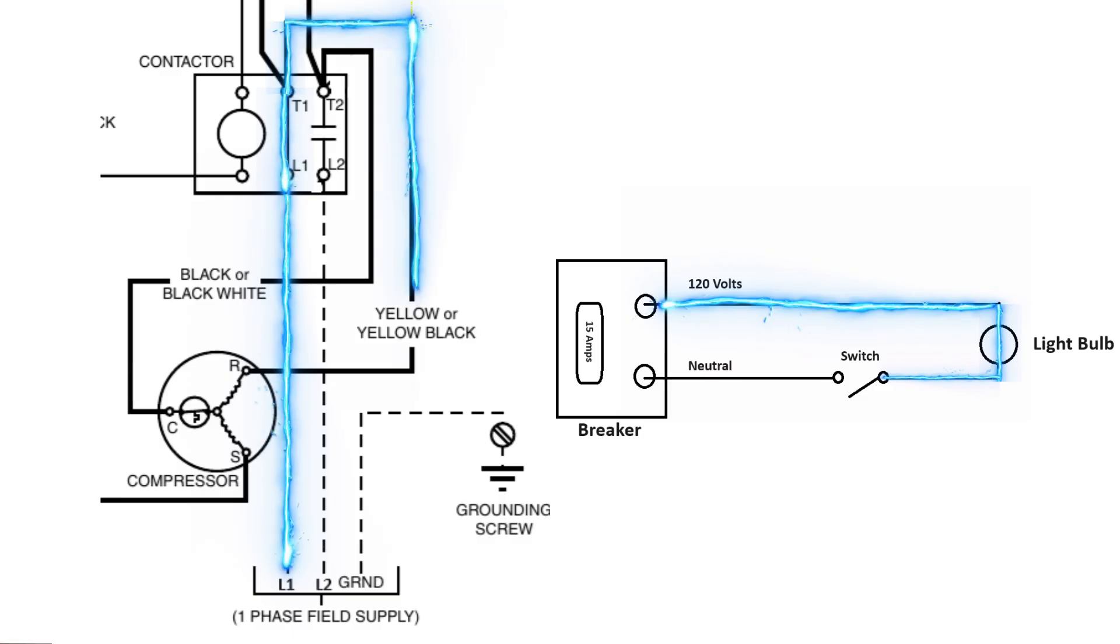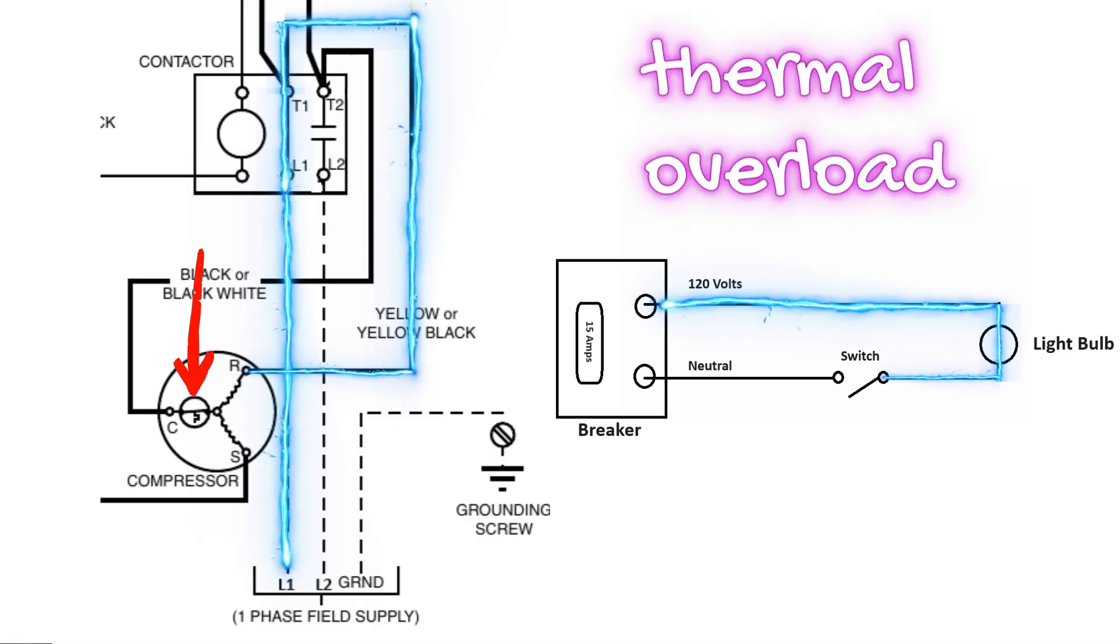And if we continue tracing this wire out, we can see it brings us all the way to the run winding on the compressor. So here we have a situation we spoke about earlier where we can have power up to a motor and the motor's not running because we do not yet have a complete circuit back to the power source. If we were to continue following this line, we can see it goes through our run winding. It goes onto our common winding and we come to a switch here.